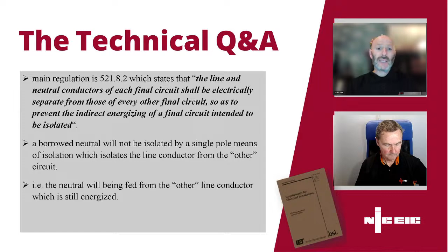Anything you'd add there? No, again, great question to be asked. This is going to occur a lot in the older installations where you find you've got the borrowed neutral. Do your checks effectively. Isolate, check, make sure it is isolated. Don't assume anything. Apply safe working practices, follow what's necessary, and just make sure that you are disconnecting the right conductors, and that you're not putting yourself or others at risk. And then you can discuss the outcome with the client on how to move forward to rectify the problem, which sometimes is not as easy as it's made out to be, but at least it's been identified and it can be addressed as well.